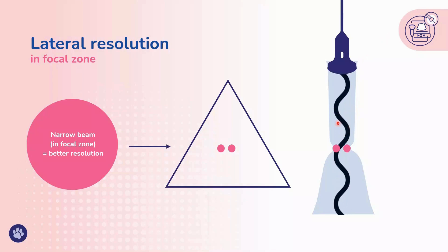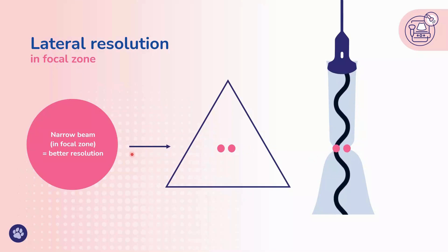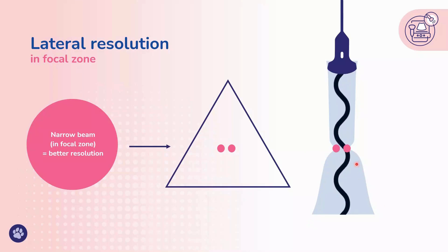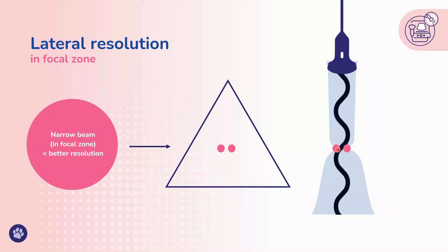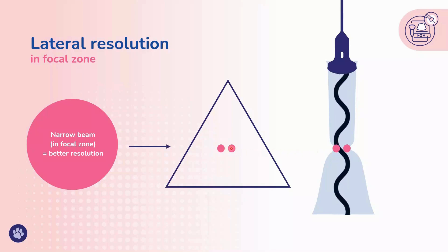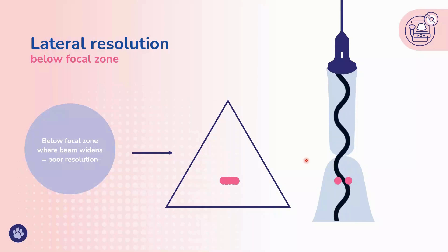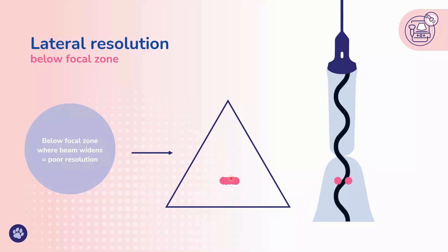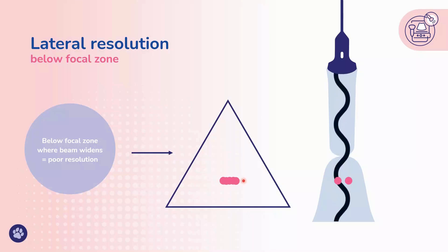Here we've got our sound beam and I'm depicting the thickness of the beam. We can see the level of the focal zone — also depicted by this arrow on our image — is where it's narrowest, and below we can see the beam widening. If we've got two lesions, we want them to be at the level of the focal zone. If they're small lesions they'll show up nice and accurate. In contrast, if the focal zone is too high above the lesions, where the beam widens, we get poor resolution and these lesions show up blurred together.